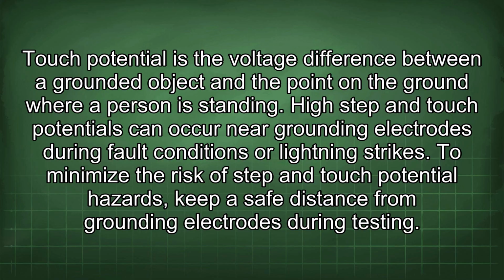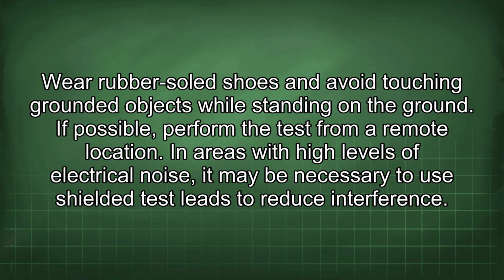To minimize the risk of step and touch potential hazards, keep a safe distance from grounding electrodes during testing. Wear rubber-soled shoes and avoid touching grounded objects while standing on the ground. If possible, perform the test from a remote location.